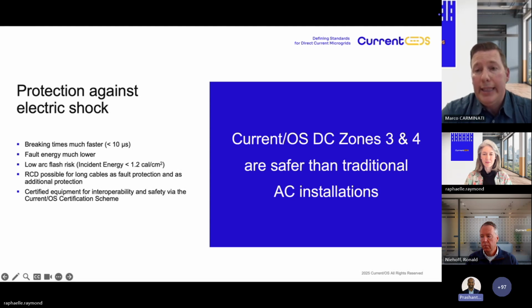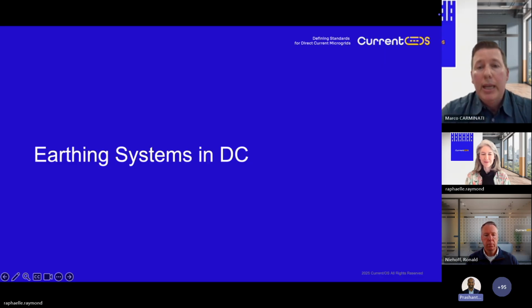So usually no personal protective equipment is required. If we have a TN-S distribution, like we will see later on, an RCD is possible for long cables as fault protection and as additional protection for direct contact. Anyway, in Current OS, we are defining a certification scheme in order to certify the equipment for interoperability and safety and more. So now let's talk about the earthing system in DC.